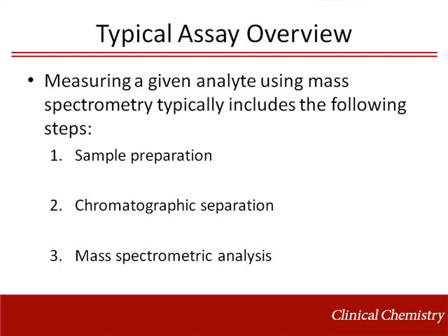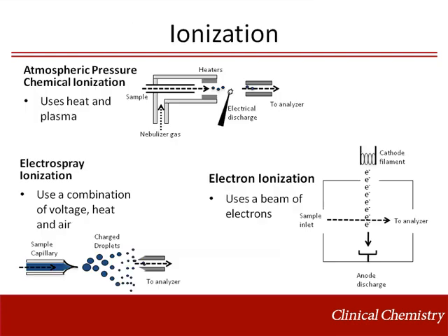The final stage of detection using a mass spectrometer is the focus of this portion of Pearls of Laboratory Medicine. In order for an analyte to be measured using mass spectrometry, it must carry a charge and be in the gas phase. For analytes introduced into the mass spectrometer as a liquid, several types of sources exist, including electrospray ionization and atmospheric pressure chemical ionization.